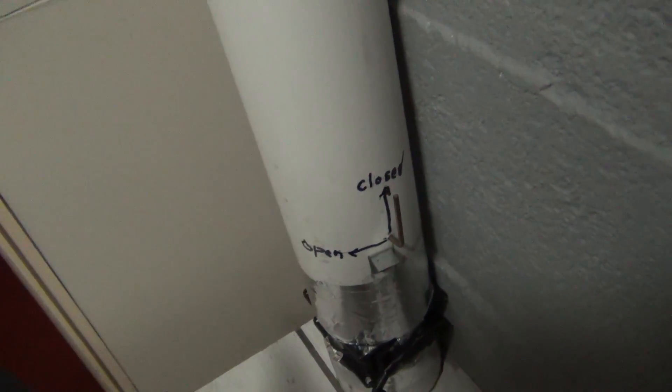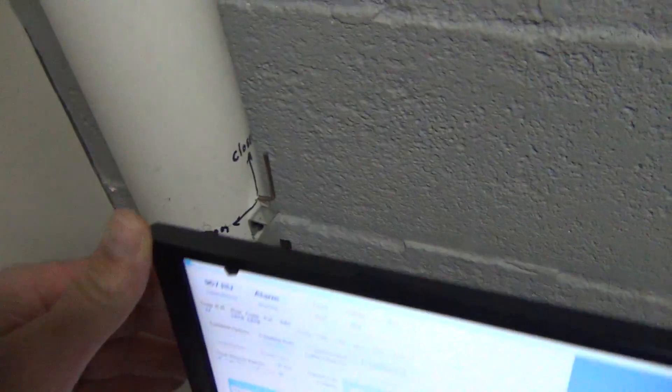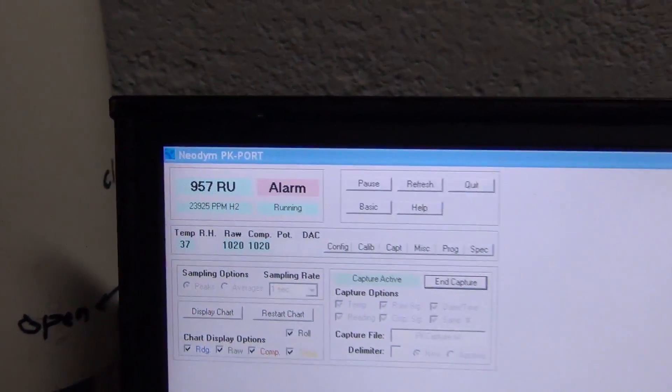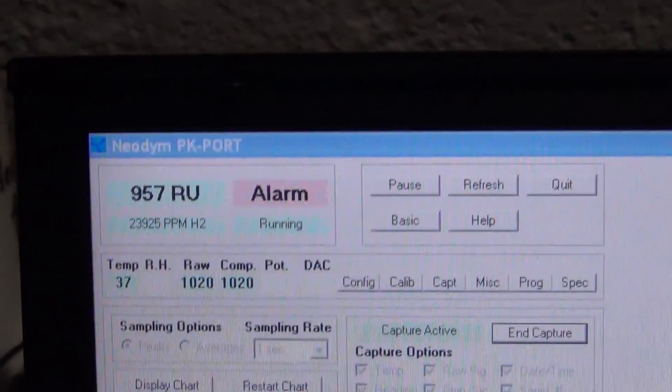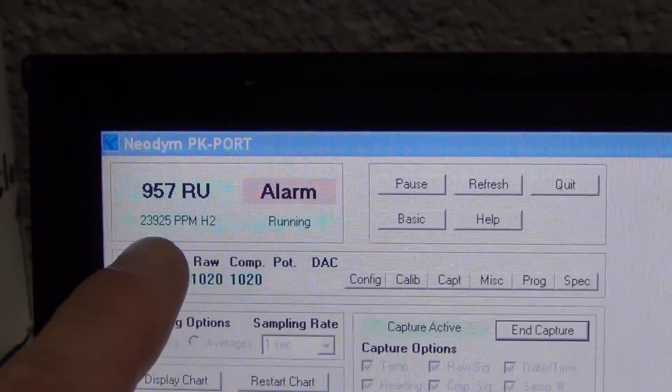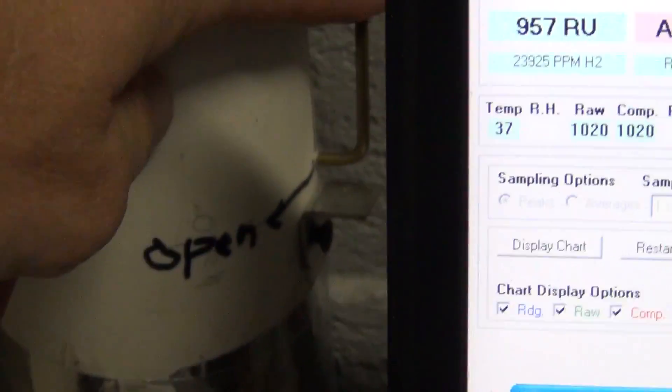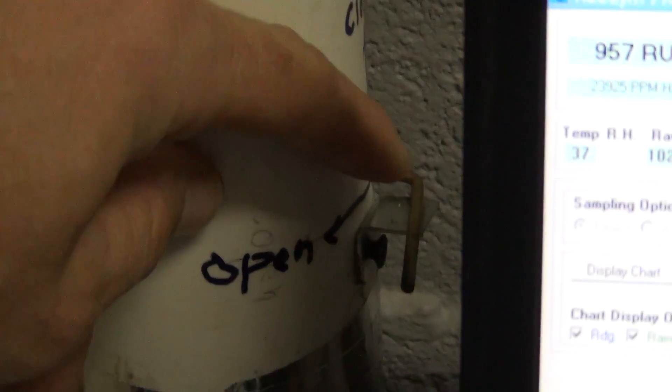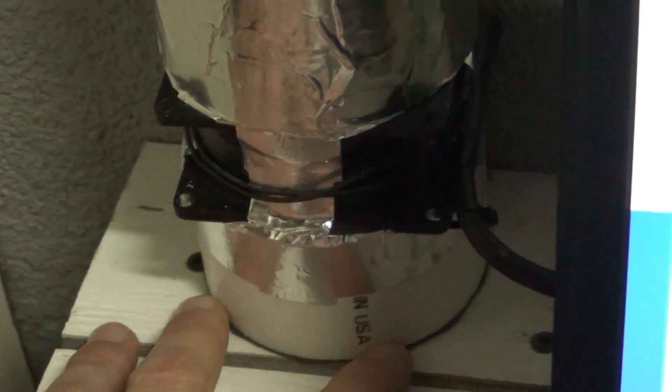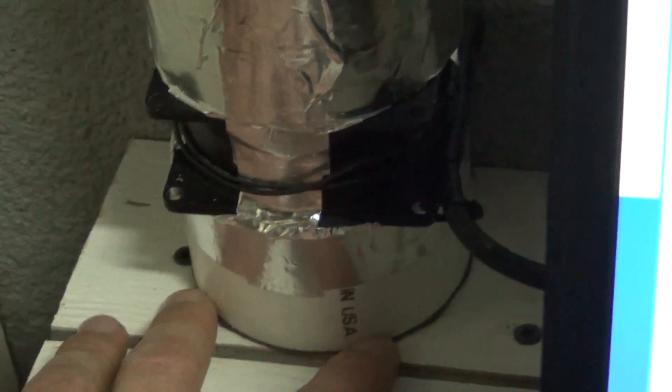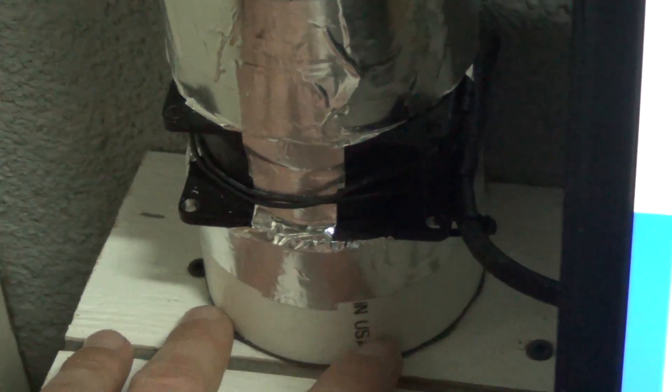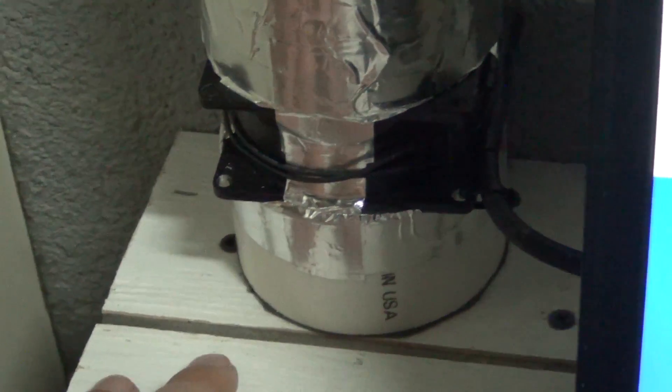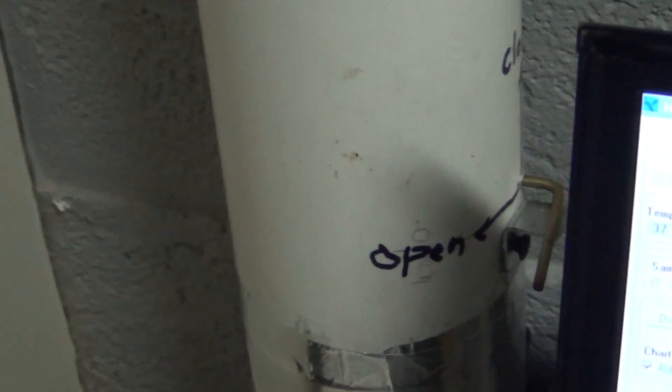And what we're going to do here now, I don't know if you can see it here. I'll zoom in a little bit here. You can see they're almost 2.4 percent here. So I'm going to go over here and now open the valve. It's just going to, basically this is a two inch pipe. Well, this is three inch, but there's a two inch hole here. And now we're going to watch the graph to see what the difference is and how good our ventilation is. Is really what we're trying to find out with this hydrogen sensor. Is this really working and do we have a good system?